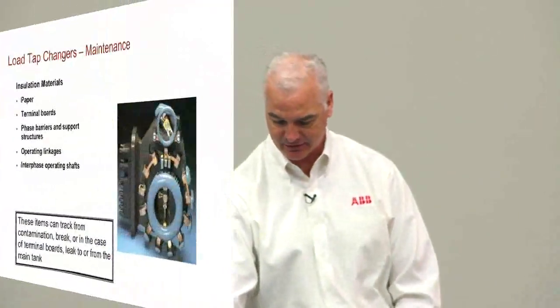And what they're trying to do is use resistive vacuum-type tap changers to limit that arcing that's going on those contacts today. But a lot of your older transformers had what they called preventative autos, so you have the arcing going on in the LTC. You get the contact wear, you get the coking as just a natural effect of an LTC.